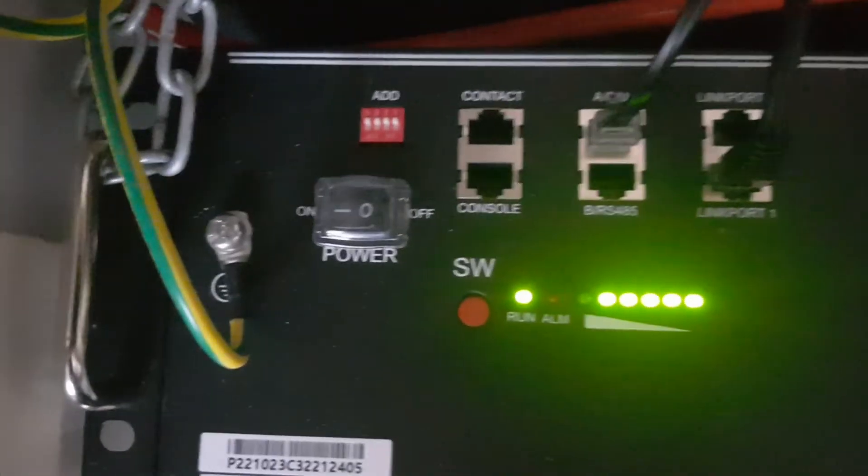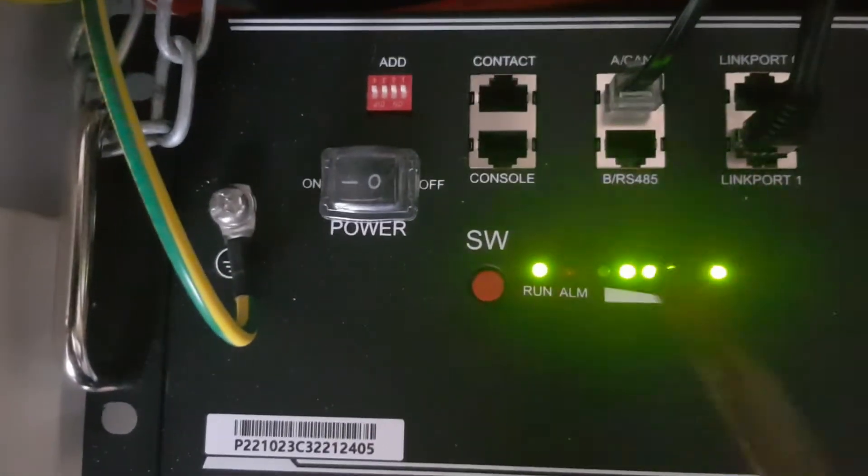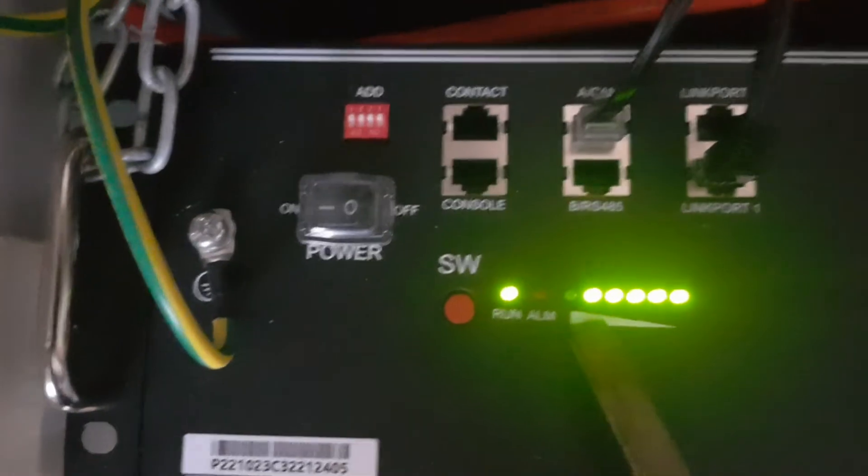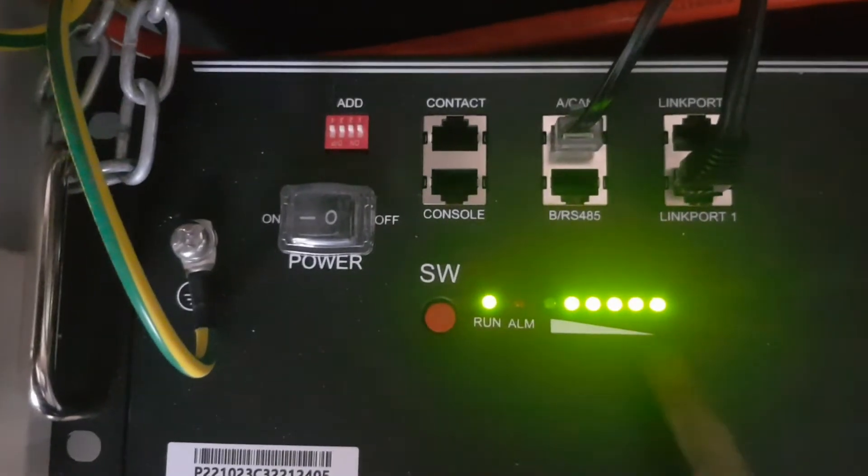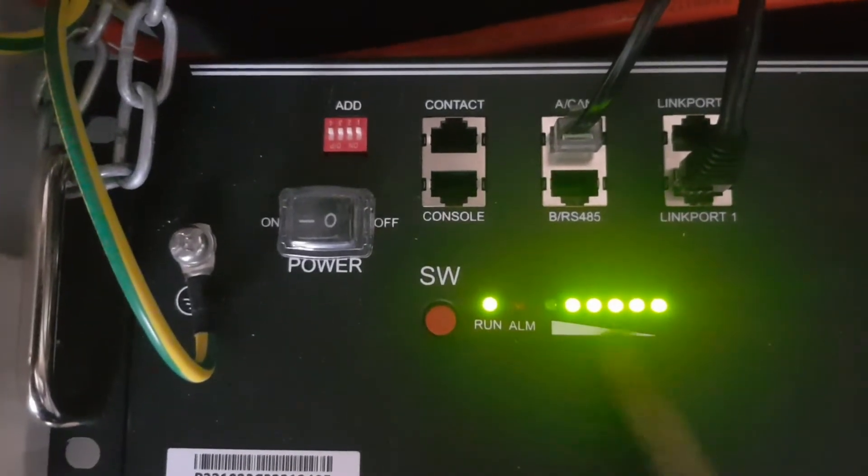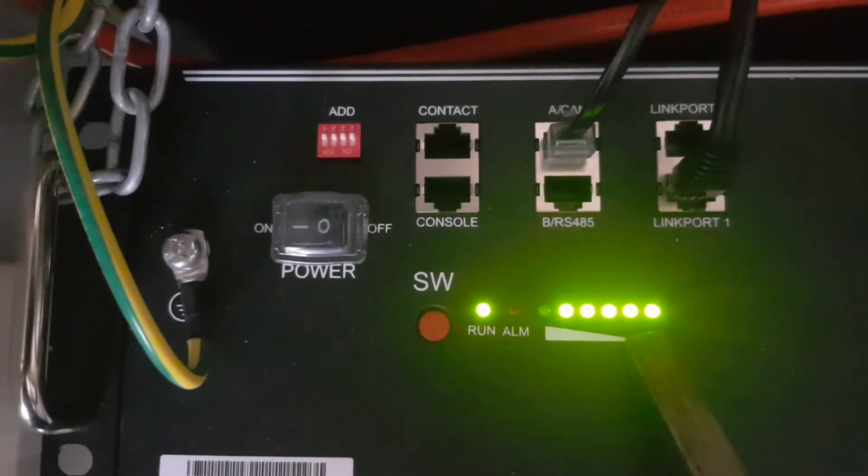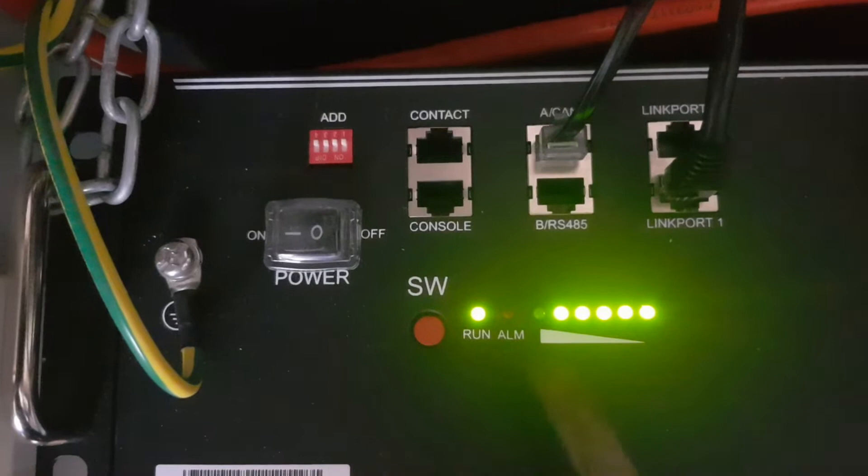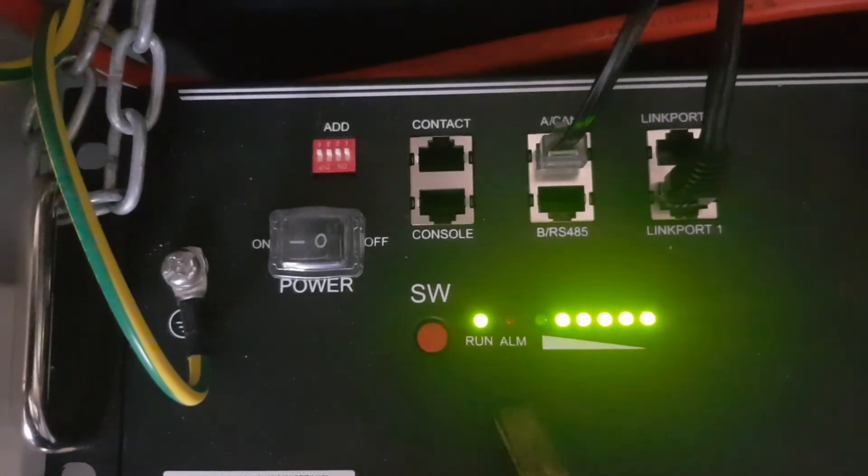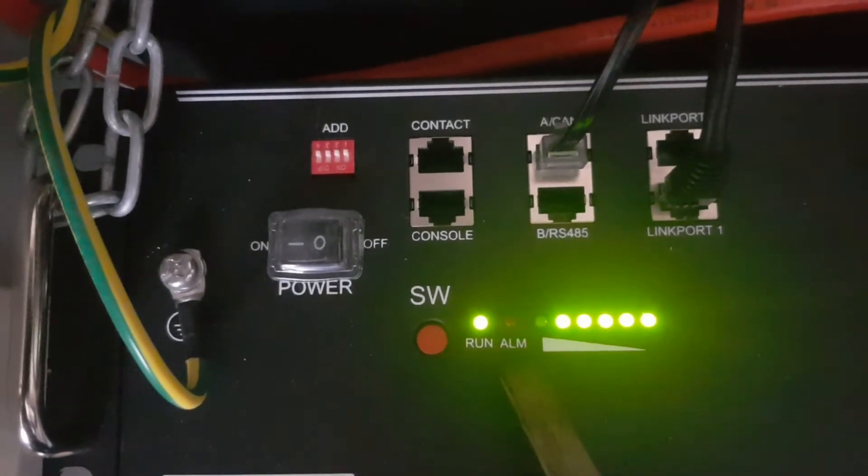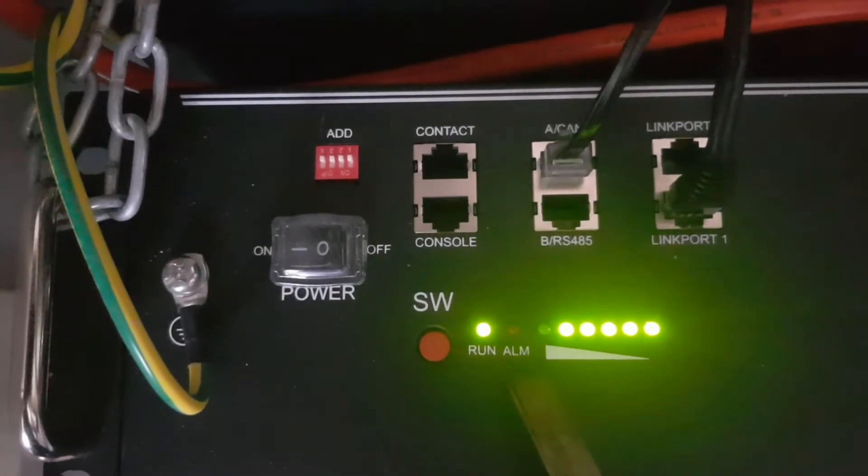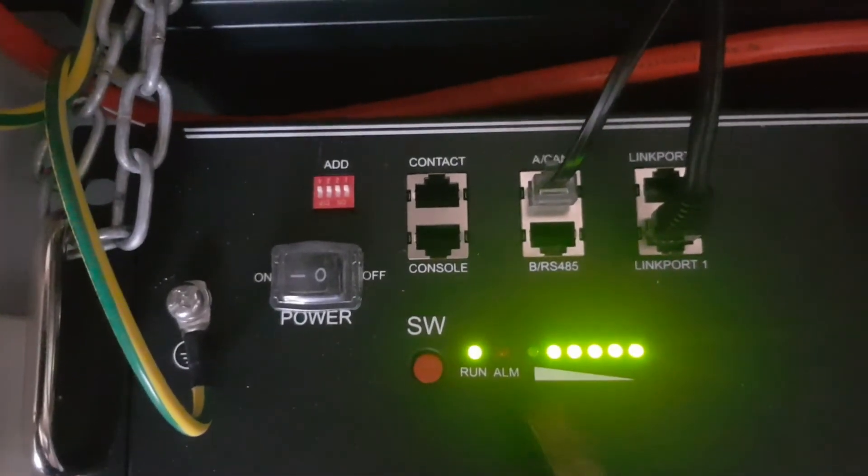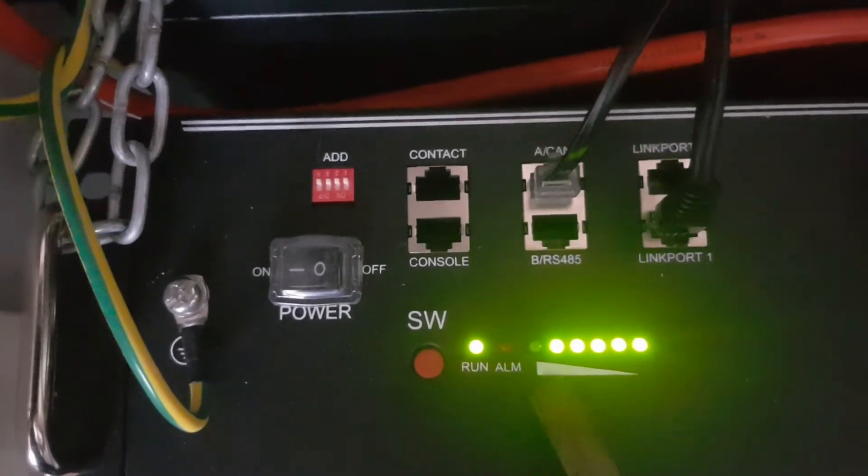Normally, if you look at the battery lights, you'll see the run light, an alarm light, and a status light for state of charge. The faulty battery will have an alarm light lit.